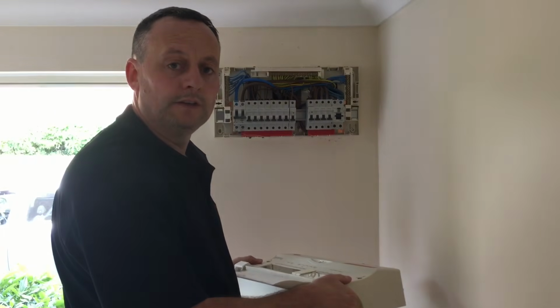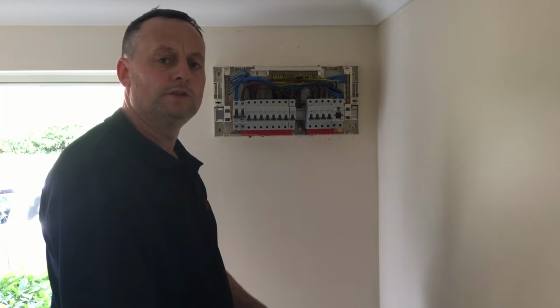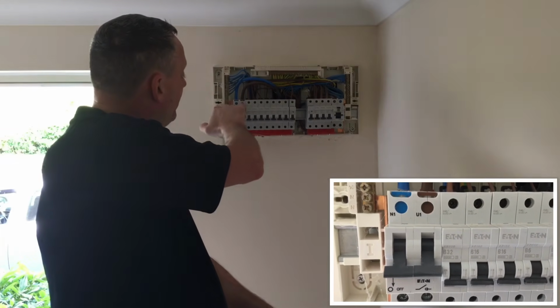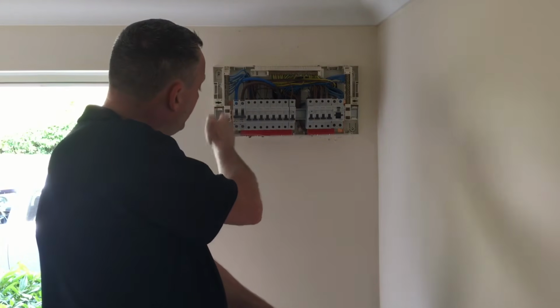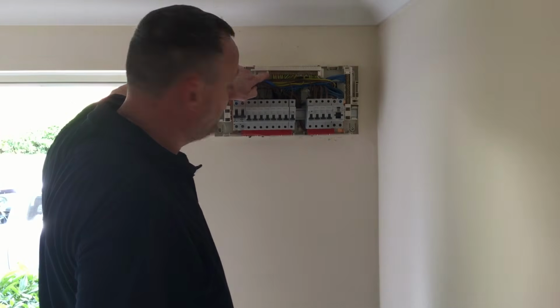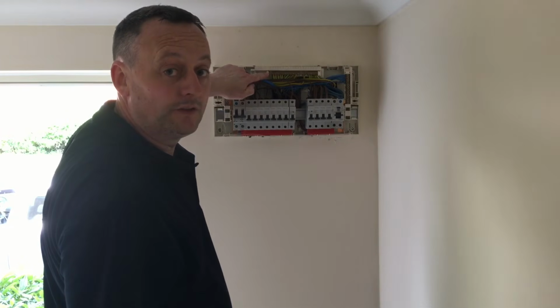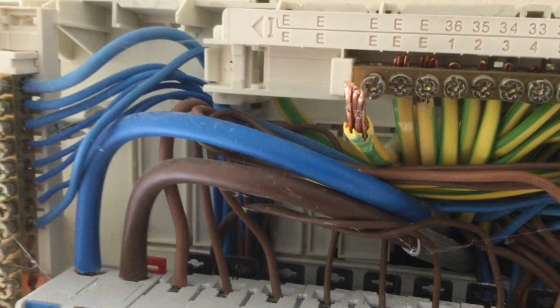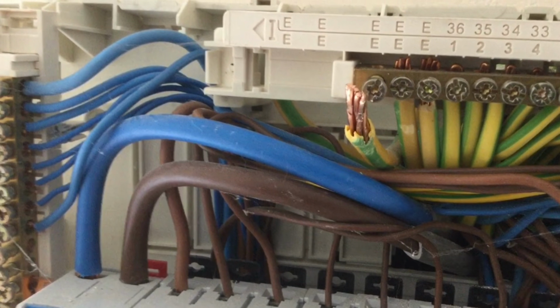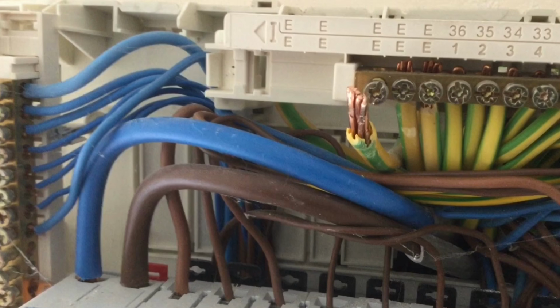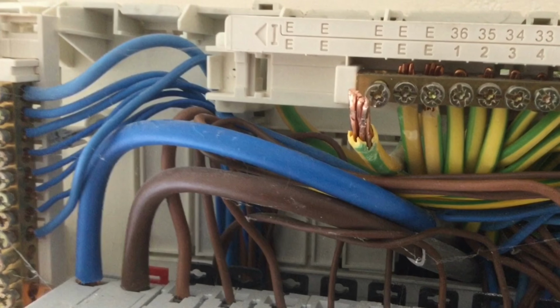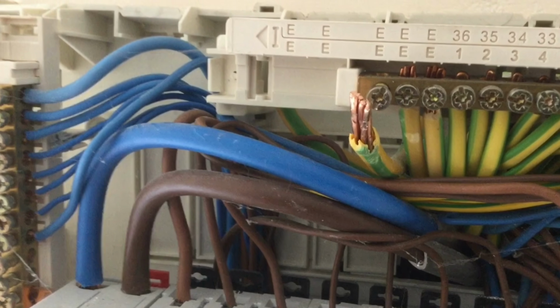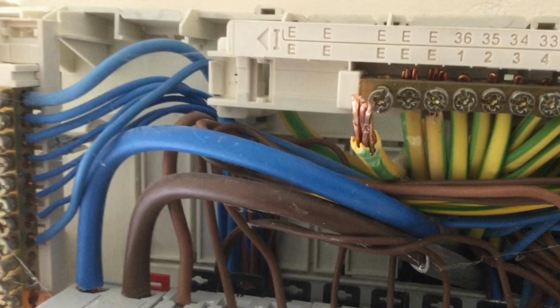Exposing the conductors underneath. So the distribution board cover is off, and we can see that even the live parts on the top of the double pole switch are shrouded from contact, and the bottom of the double pole switch going through has all been isolated. Therefore I can disconnect my 16mm earthing conductor in order to perform the test. With the 16mm earthing conductor removed from the main earth terminal, the parallel earth paths created by things such as gas, water and oil have been removed, giving you a true external earth fault loop impedance of the installation.